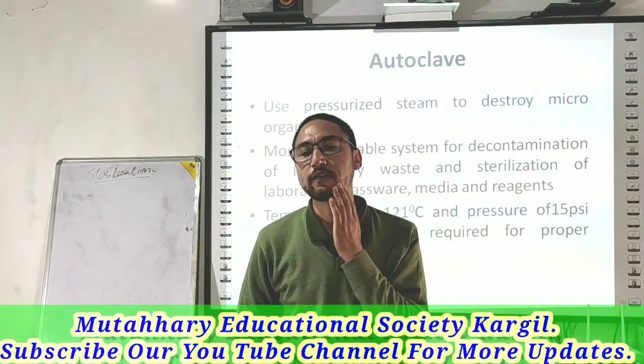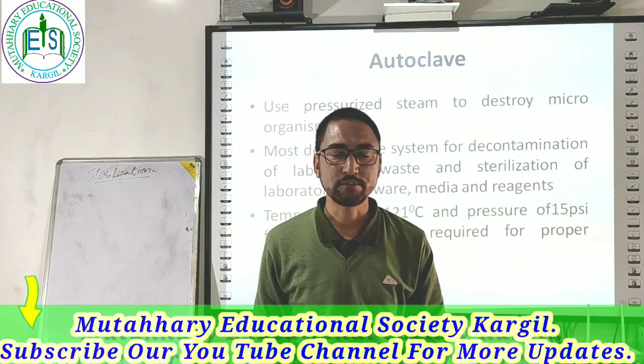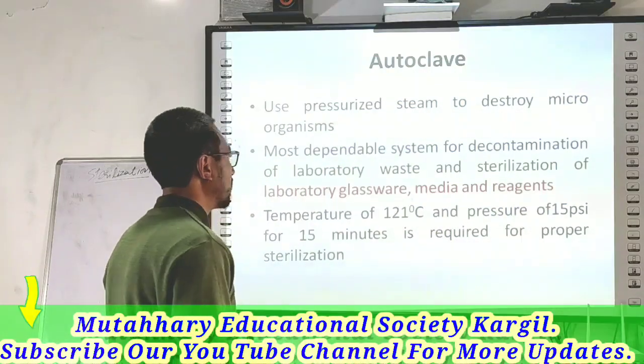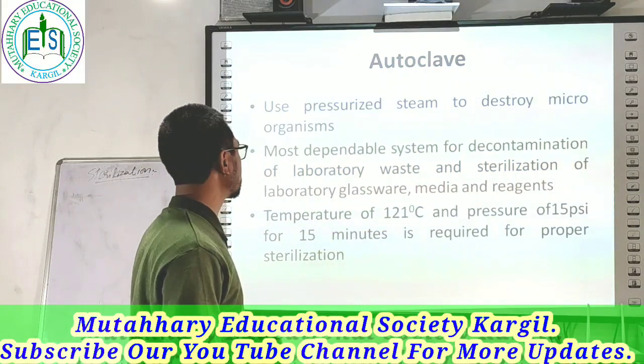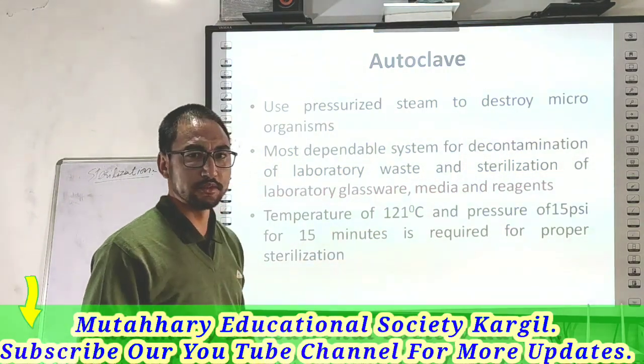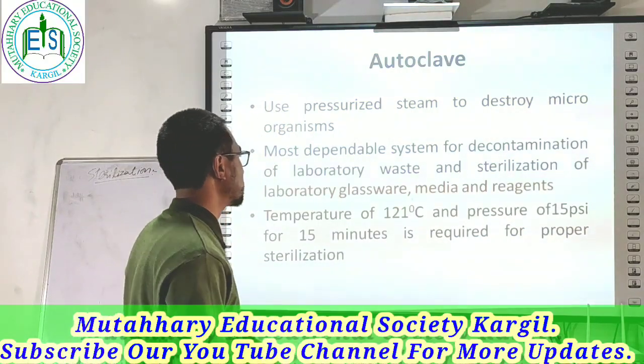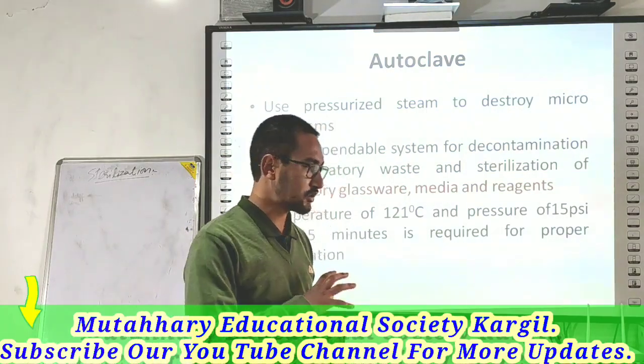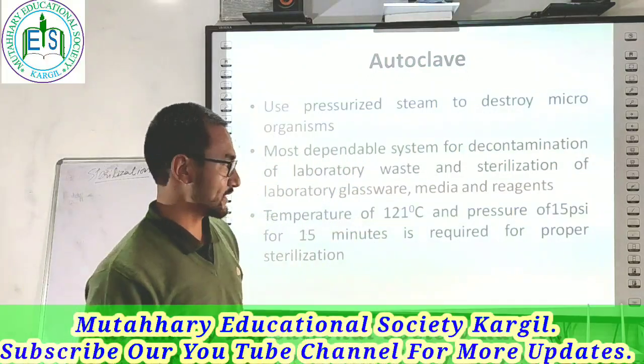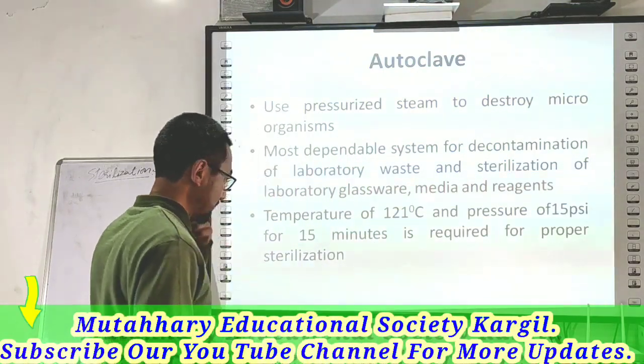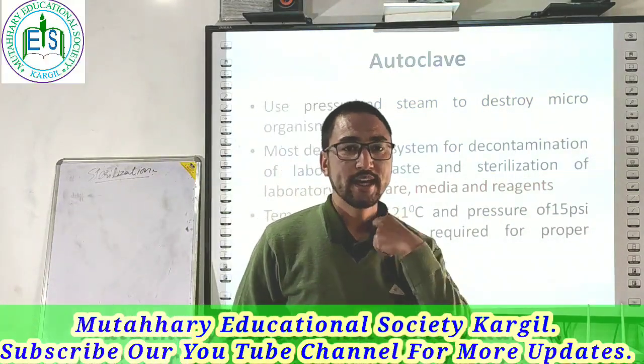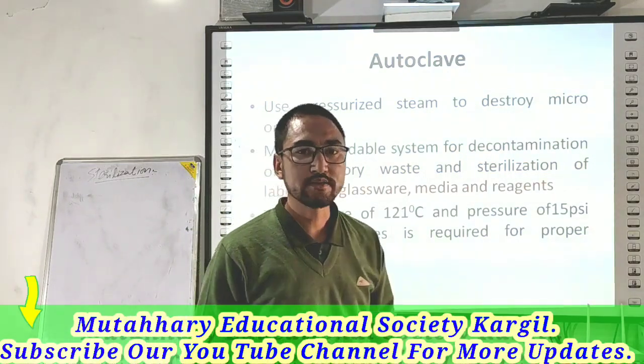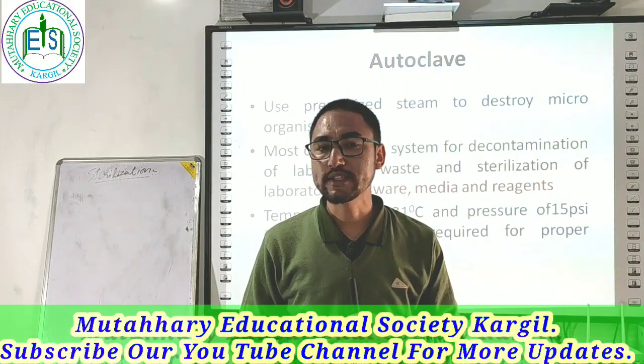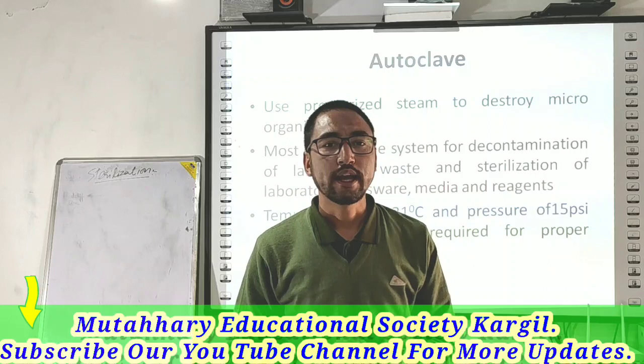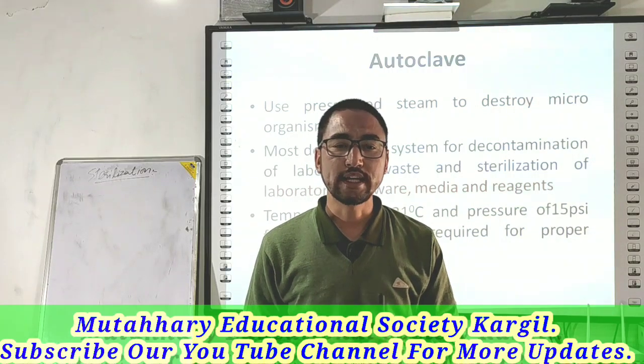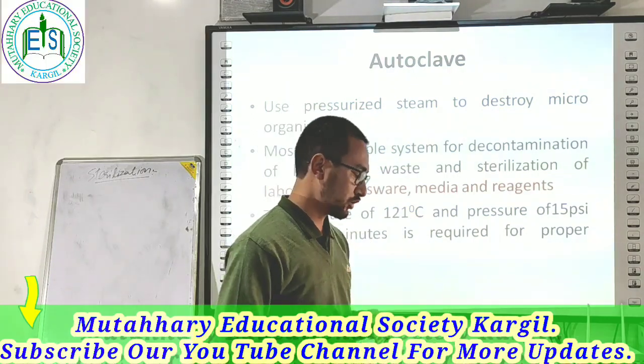For steam sterilization we have a specific technique called autoclaving, and the machine is called an autoclave. The autoclave uses pressurized steam to destroy microorganisms, and it is the most dependable system for decontamination of laboratory waste and sterilization of laboratory glassware, media and reagents. These are the three important things where we use autoclaving as a sterilization method. The temperature is 121 degrees Celsius, the pressure is 15 psi, and the time required is around 15 minutes. That means 121 degrees Celsius, 15 psi of pressure, and 15 minutes are required in order to remove any kind of bacterial spores present within the media or over the surface of the materials.